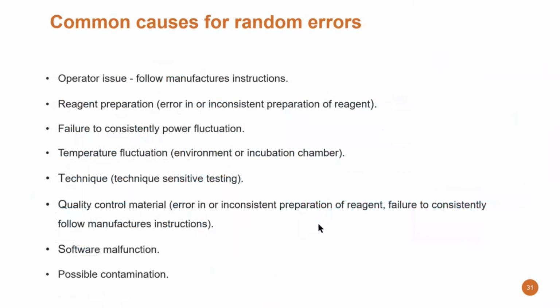Common causes for random errors: the operator issue. I'm finger pointing again at human error and human behavior, as my advice is please read the instruction carefully and refer to the instruction to better understand why failures or errors may happen. Reagent preparation error, or inconsistent preparation of the reagent. These days, most of the reagents are ready to use, but still consider that you are using the reagents at a correct temperature.